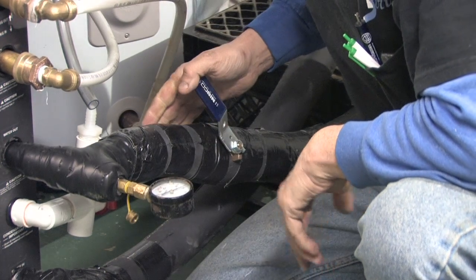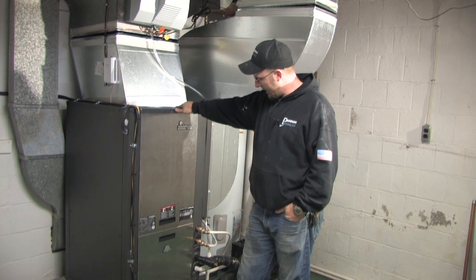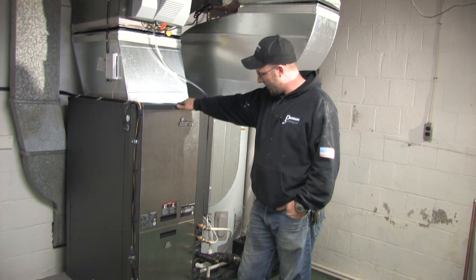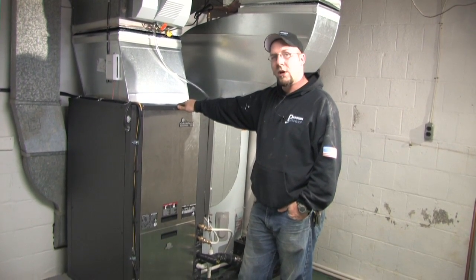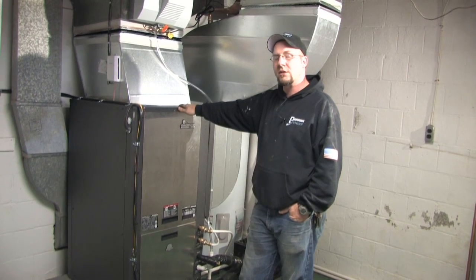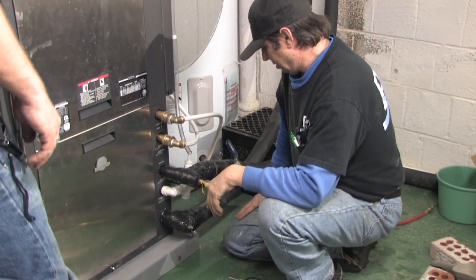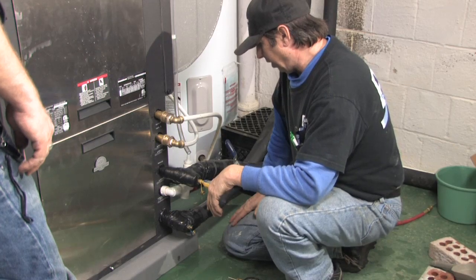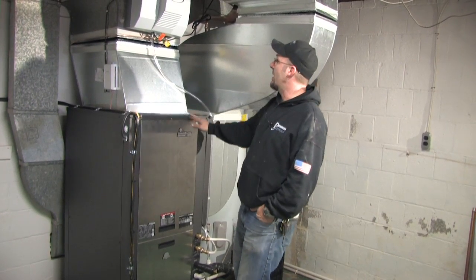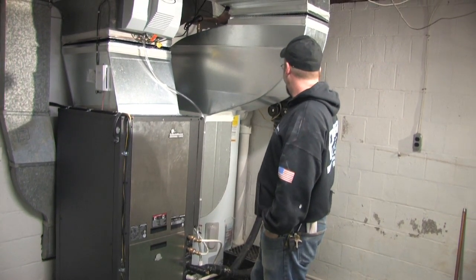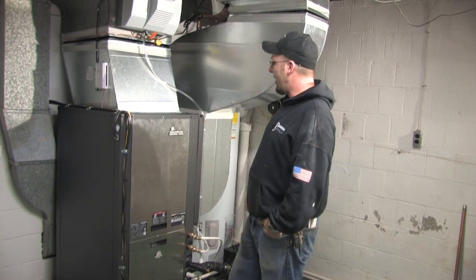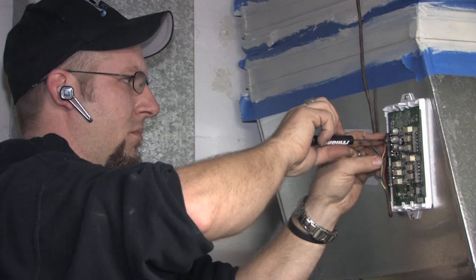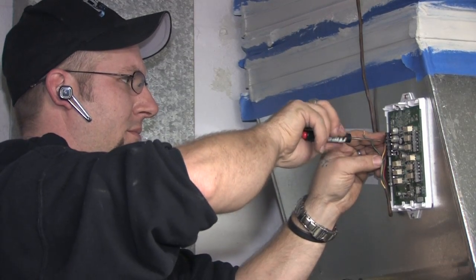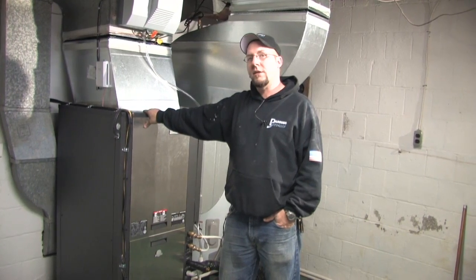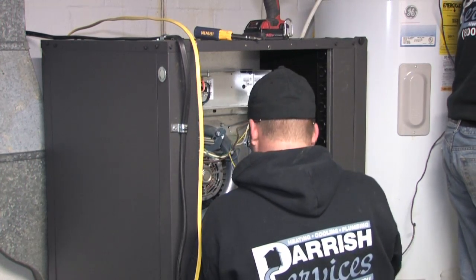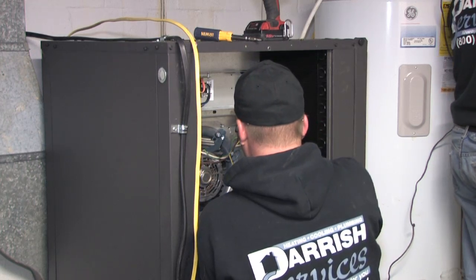We tested it with one pump after we got it set up, and then was able to test it with both pumps running, and it actually doubled from 16,000 to just over 30,000 BTUs on the 3-ton unit, which the book rating is 27,000, so it's doing really well. We have, for the heat kit, we installed an outdoor temperature sensor so that the heat kit won't run above 40 degrees. It won't allow it to come on.